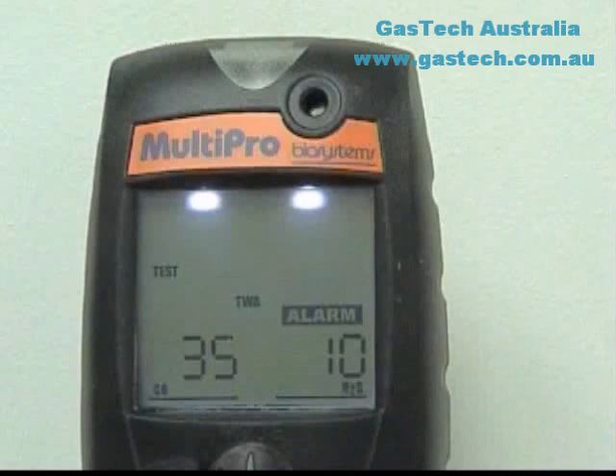Time-weighted average, or TWA values, are calculated by taking the sum of exposure to a particular toxic gas in the current operating session in terms of parts per million hours, and dividing by an 8-hour period. The default TWA alarm for the Multipro's CO sensor is 35 parts per million. The default TWA value for hydrogen sulfide is 10 parts per million.